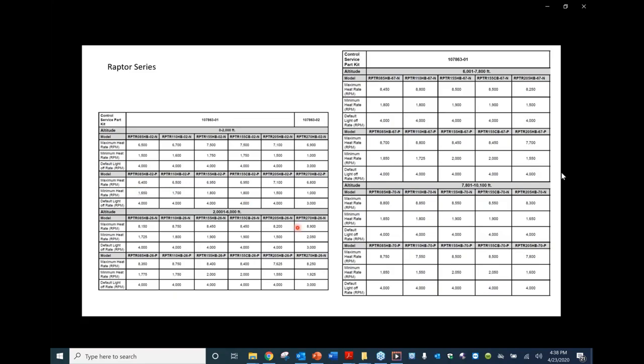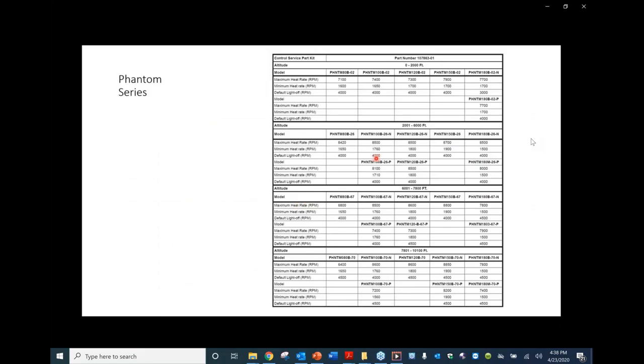For the most part, the light off rates stay the same for natural and for propane. In some instances, depending if there's any combustion noise or a little bit of noise at light off, we will raise and/or lower the light off speeds. That would be done after we dial it in with a combustion analyzer. And the same chart is also found for the Phantom series. If it's blank, we don't have a listing for it.